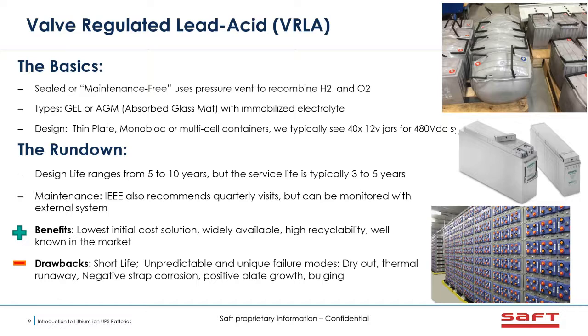The main benefit is that they are the lowest initial cost solution. They're widely available, highly recyclable, and very well known in the marketplace. However, the drawback is that short life. Again, they do fail unpredictably, and they have a lot of unique failure modes associated with them, as far as dry out, thermal runaway, negative strap corrosion, positive plate growth, or bulging. So a lot of different failure modes associated with this technology.